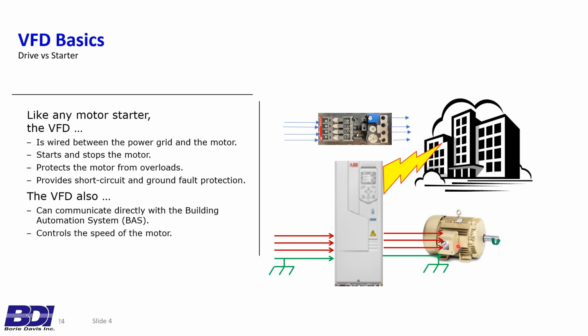And of course, the drive gives you 0 to 60 hertz typical application, allowing you to run any speed from 0 to 60 hertz relative to generally some minimum frequency or minimum speed that is set by the application itself. But you only get one speed out of the starter. All ahead full, 460 volts, 60 hertz, nameplate RPM basically. So much more control with the variable frequency drive.